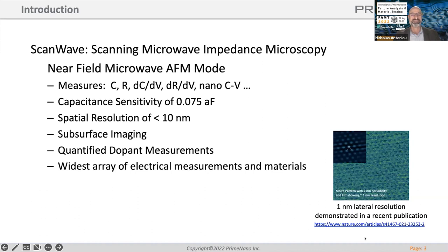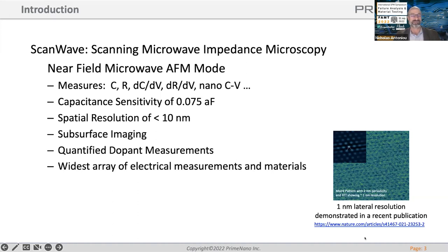It's a technology that came out of Stanford University and we have exclusive rights to it. It's a near-field microwave AFM mode — one of the younger techniques, so there are still a lot of applications to discover. What we measure is relative capacitance and resistance. We can do dCdV, dRdV, nano-CV — quite a lot of capabilities in the electrical realm. This is microwave-based, so we're not actually sending a current through the sample. We've pushed the sensitivity of the system — we finally measured it with NIST and it's about 0.075 attofarads.